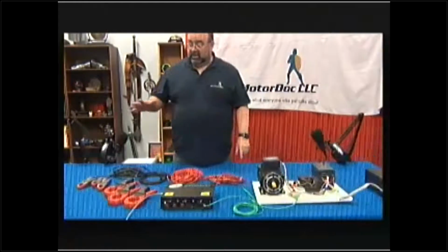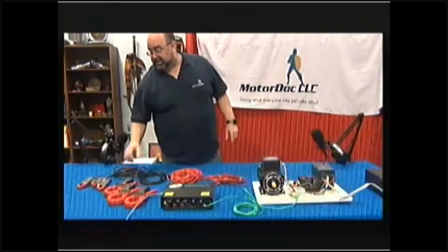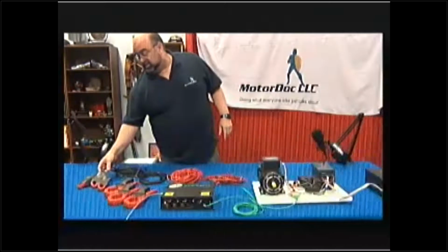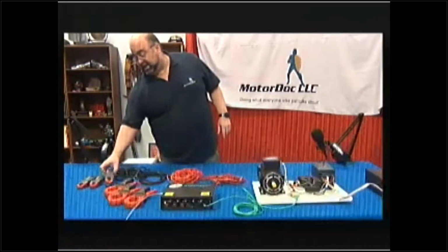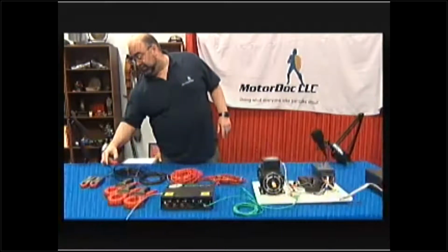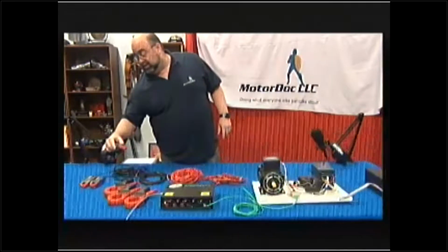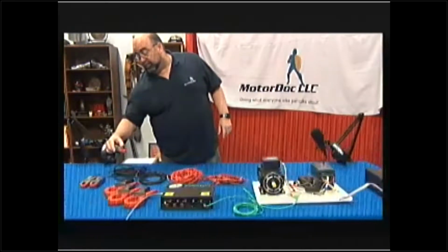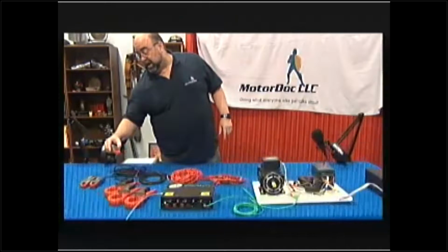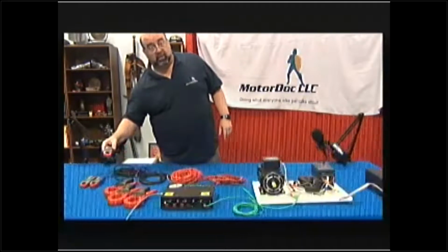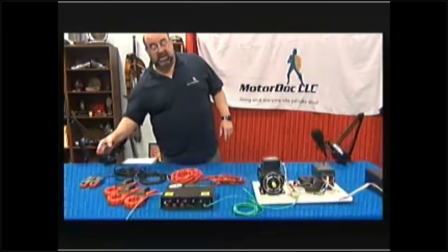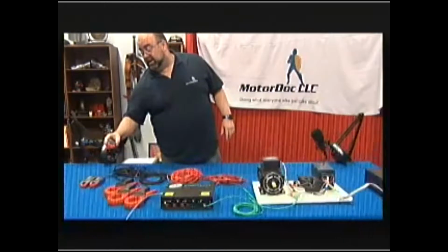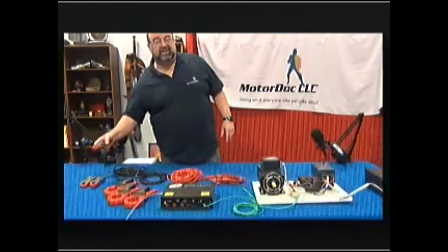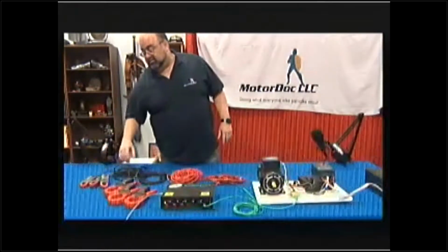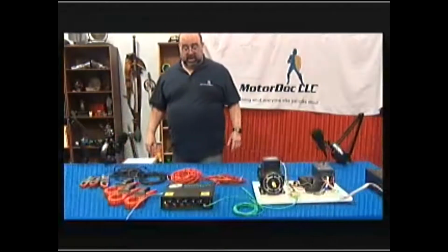What comes with this is 1,000 amp clamps, and these here are 200 amp clamps, which actually have two settings. Little secret: always use the 10 millivolt per amp setting. When I've tried using the other one to get the lower current reading, in order to take data off the back of a Multilin, it usually knocks out some of the signals I'm looking at.